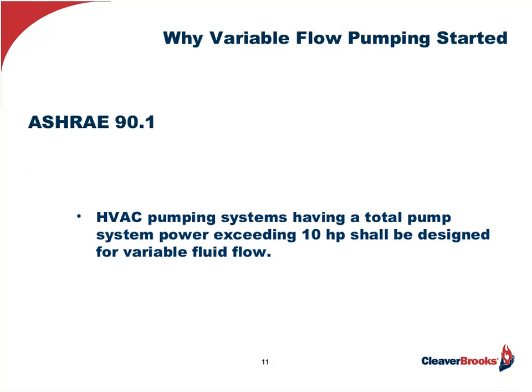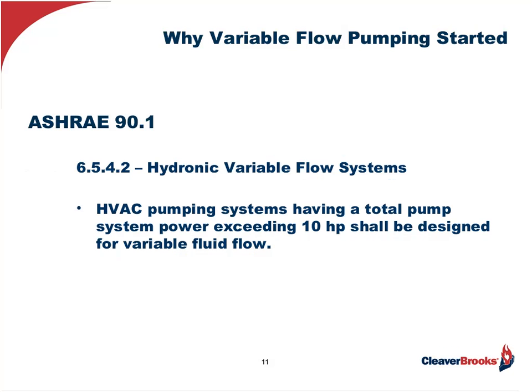Now, Steve mentioned 90.1. 90.1 originally came about after the first Arab oil embargo and the first energy crisis in the mid-70s. They started looking at ways to conserve energy, and then continually it's been updated, and in fact now we're in version 2013. It basically tells us that we have to have variable flow pumping if our pump horsepower exceeds a total of 10. Now, while that will save us energy, and it's a good thing to do, the problem we've had in the past is that a lot of the boilers out there have not been designed for variable flow. And that's part of the reason why people began using primary, secondary pumping.